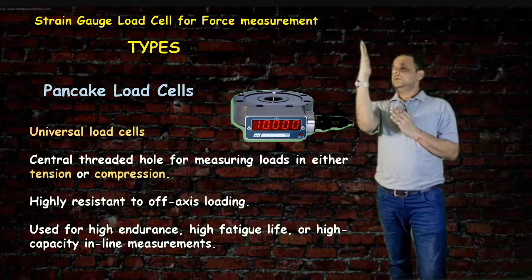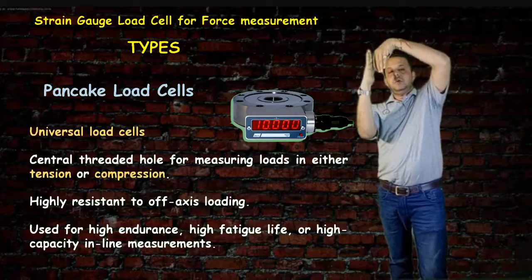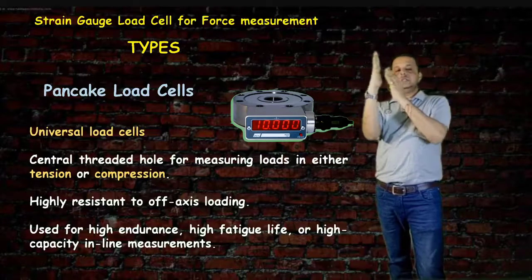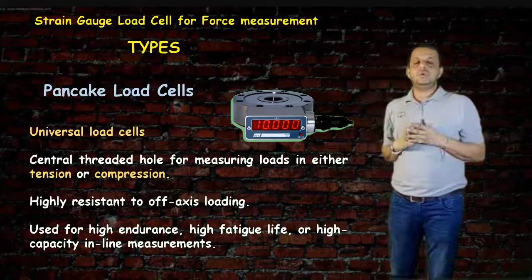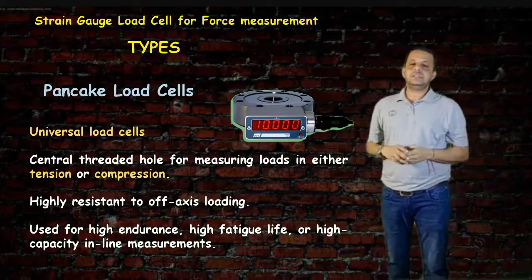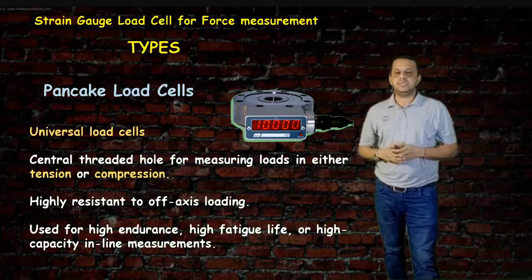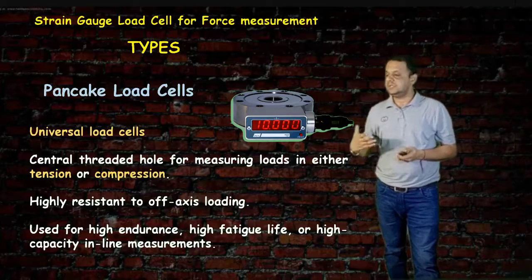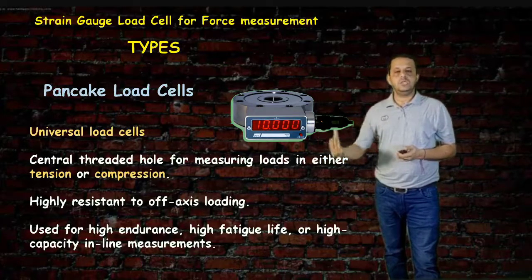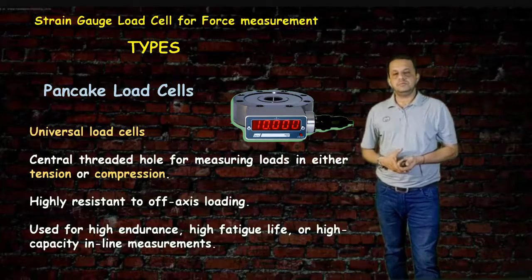Like if a rod is inserted in our load cell, and if it is moved by some other off-axis loading, it will be able to handle it. And it is used again for high endurance applications and inline measurement. Inline means the process is going on and you have to measure it.